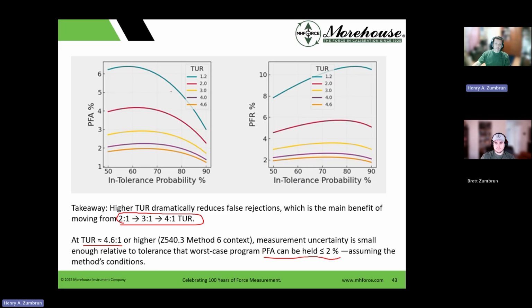So if we look at this, these are all risk curves with different TURs. PFA percentage with a 1.2 at 6% in-tolerance probability, or end of period reliability. And then you look at the PFR percentage, 10 is higher on that one than it is there. So again, you're just going to do more rework the higher the uncertainty. And once you get down to these 4.6 numbers, this low number, your PFA and your PFR, if I can highlight it right there, Brett, is well under 2% for both of these curves. In fact, at 4 to 1, it just nips over.